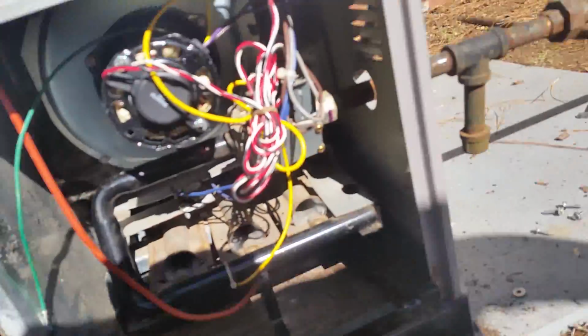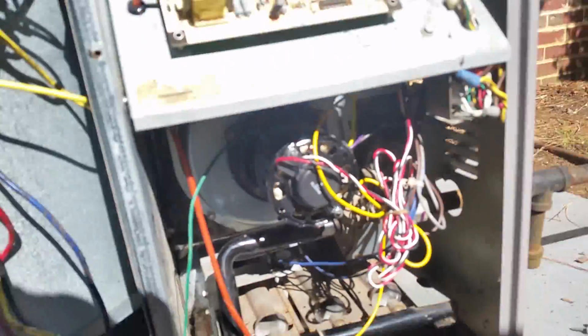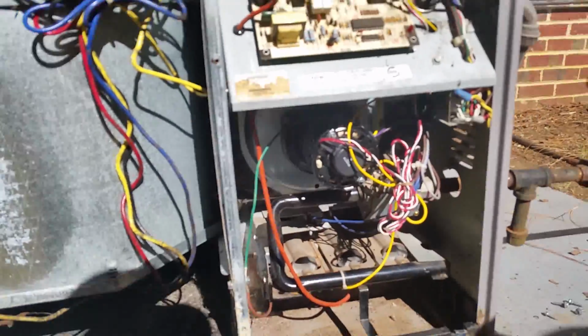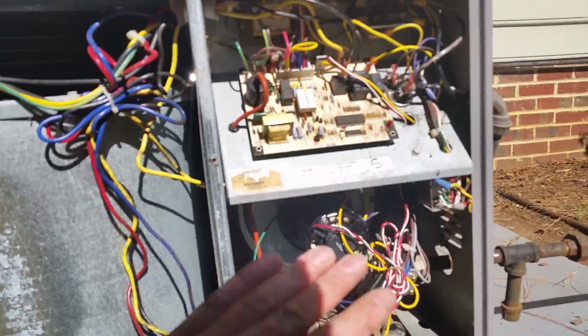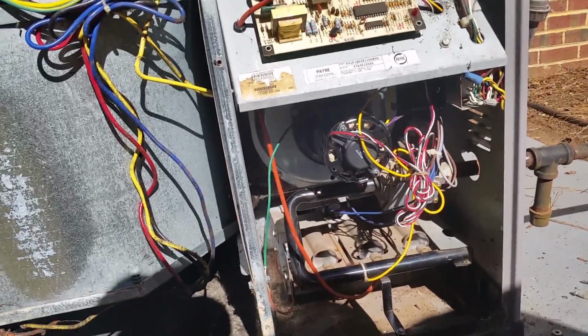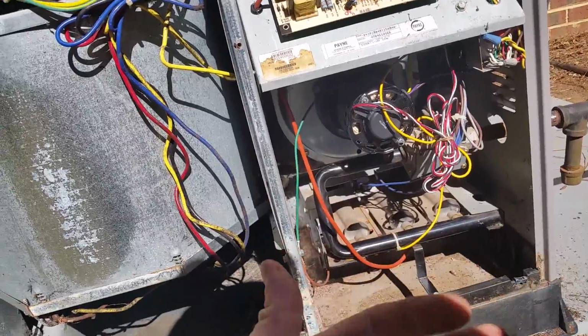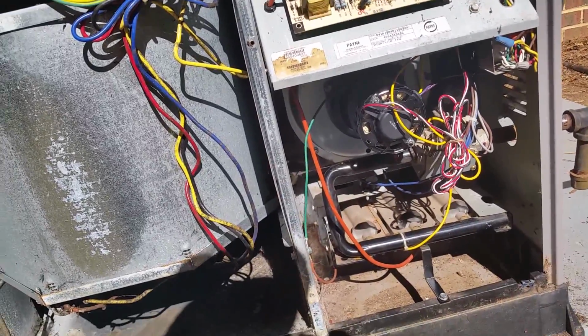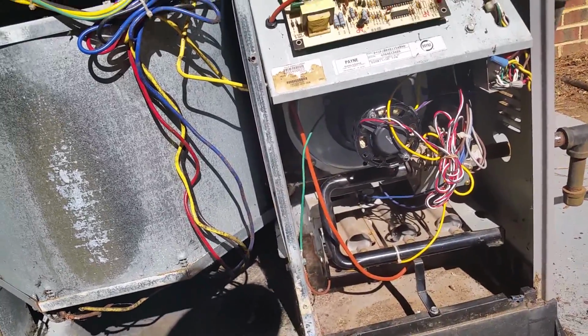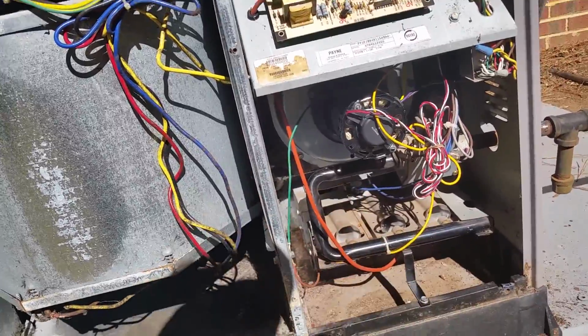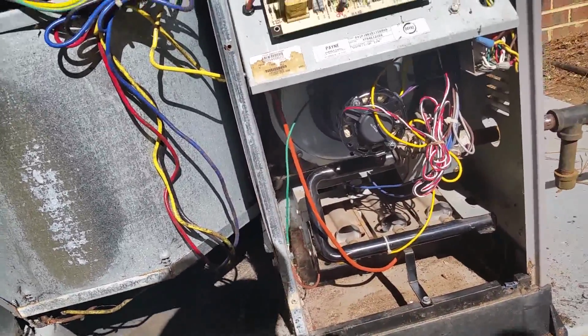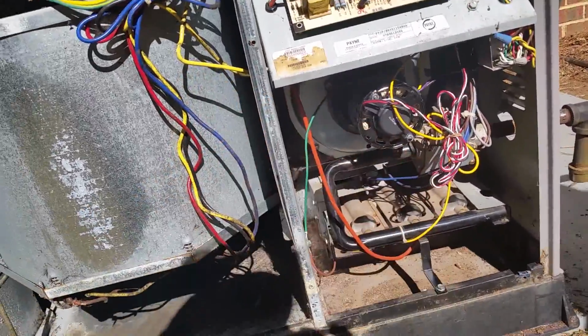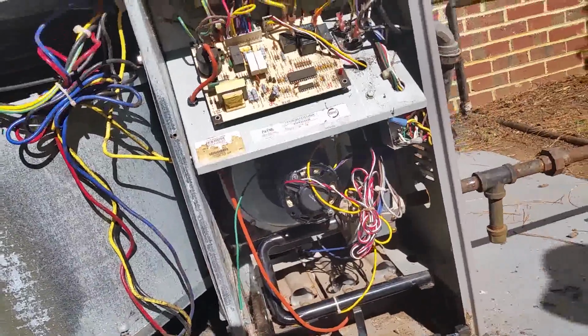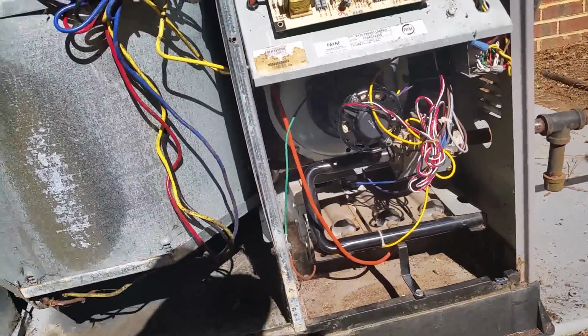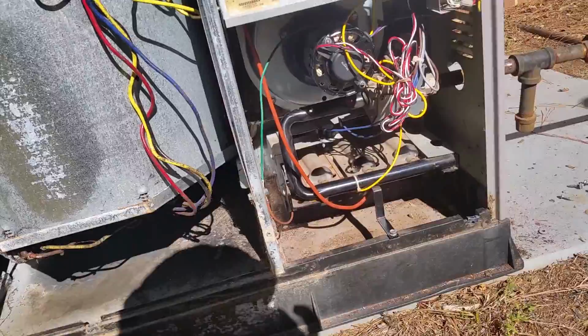Okay, so she's firing. Everything looks good. We're still going to wait just to make sure that when that firewall plate heats up, it's not going to warp, and you're not going to get a grinding between the squirrel cage and the fire plate wall. Because if we get that, then we'll have to adjust. But I don't think this one's going to do it. I usually wait about 15 minutes, and that's good enough time.